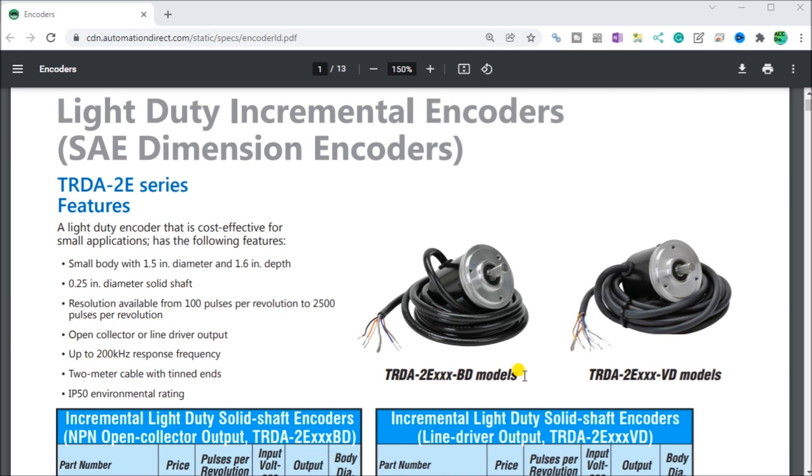Due to the speed of the inputs, they function on the BRX Do More PLC asynchronously with the PLC scan time. We will continue looking at the high-speed inputs by examining the pulse catch mode. The pulse catch mode will be set up using the Z phase of our incremental encoder. Pulses will be counted using input directly in the ladder logic and using the pulse catch bit. Comparisons will be made between the two counts and the output will be turned on when they are different.